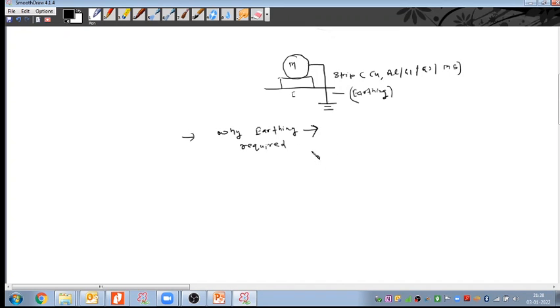Why earthing? Okay, I'll take your point and let us understand it in an overall view. First of all, suppose we have placed this equipment above the ground. I understood everyone's reply that it is for the safety of equipment and person, that is okay. But let us understand some other points also. As we know, any electrical equipment has an inner conductor, then insulation, and then an outer enclosure. Suppose, due to the aging period or weak insulation material, this insulation fails, then the current will flow on the outer enclosure.